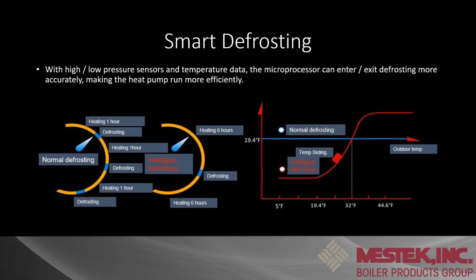All right, so we're looking at high pressure and low pressure. As that coil starts to block up because of the icing, pressure is going to go up. We're going to kick ourselves into defrost, pressure will go down, we'll go back into normal operation, and it's a smoother transfer as far as the defrost goes.